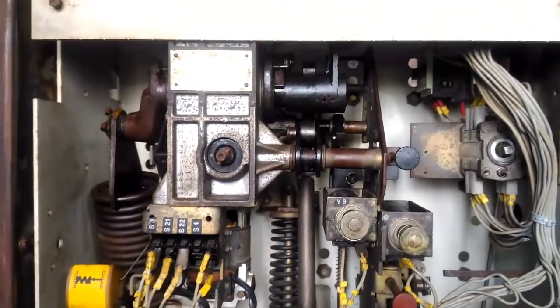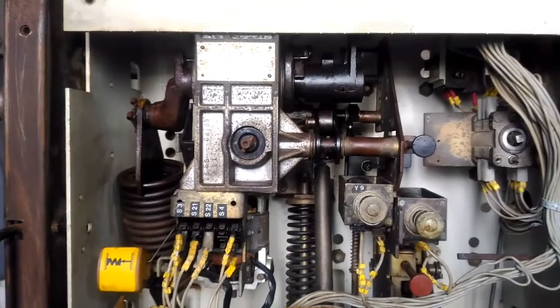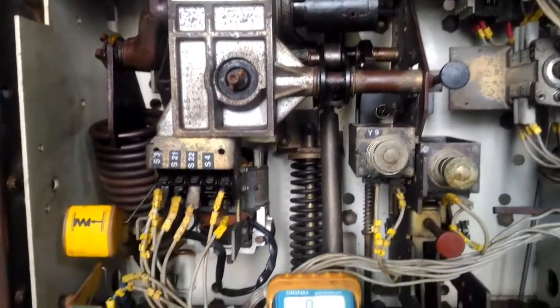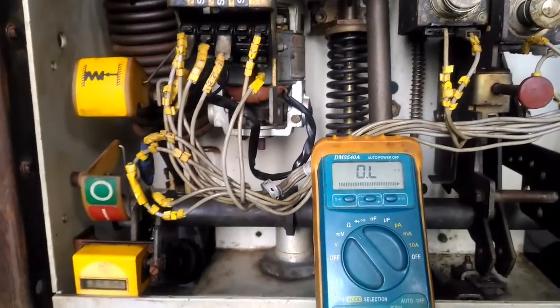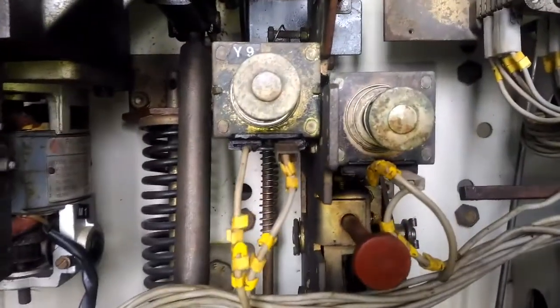After doing the thorough maintenance and cleaning of the circuit breaker, we are now checking the trip coil and close coil of the circuit breakers, along with the control circuit, spring, etc.